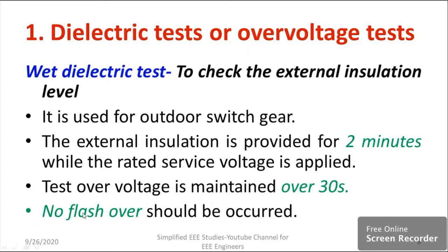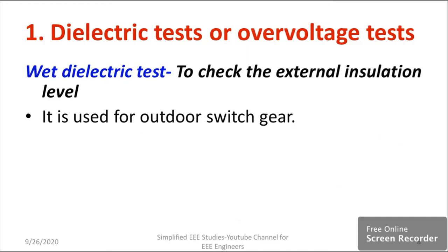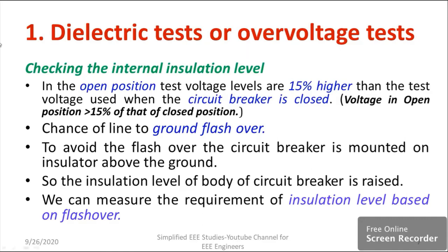If any flashover occurs, you can say that the external insulation which you have provided to your test circuit breaker is not sufficient, so you have to replace the particular test piece. Okay, so that's the scenario. So we have done both the internal insulation test as well as the external insulation test. For both cases, we need to make sure that no flashover occurs. Remember, in case of internal insulation testing, I already discussed the condition you have to remember. This is your condition for conducting the internal insulation testing. Okay.